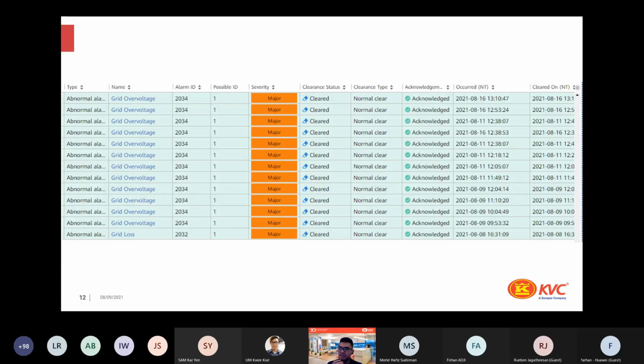This is an example from a plant. In Malaysia, I'd say one of the most frequent alarms we usually face is grid over voltage, due to fluctuation of the incoming voltage from the grid. I receive a lot of feedback from customers saying their inverter is always on and off intermittently. Whenever they look into the inverter, it seems fine, but maybe after about 5 minutes it goes off and then comes back on again.